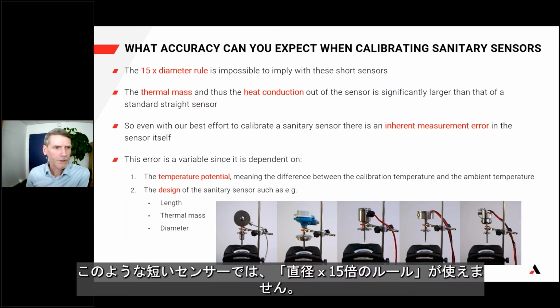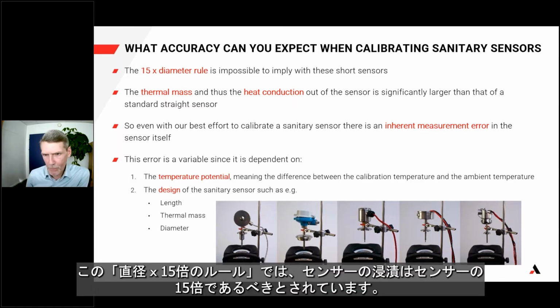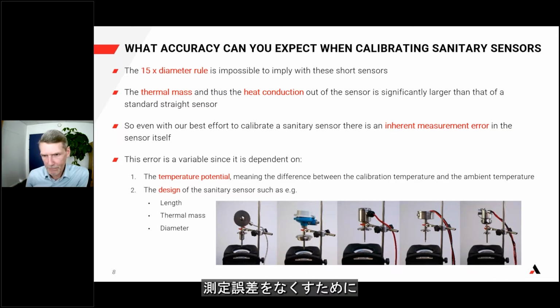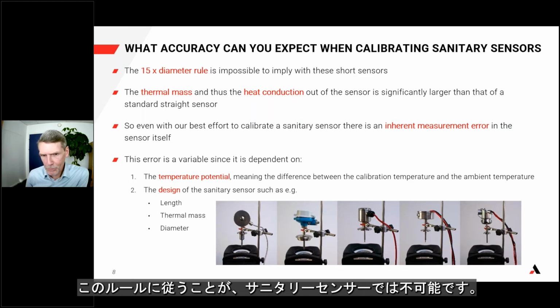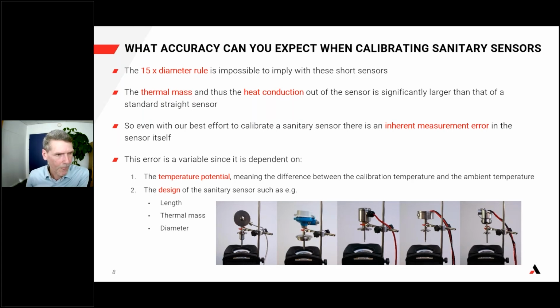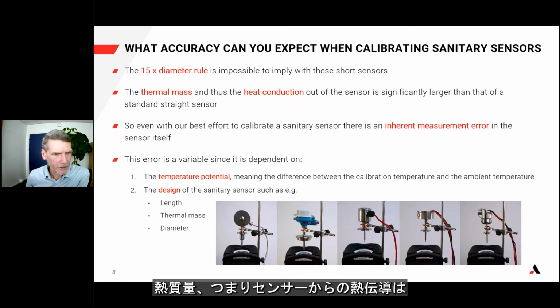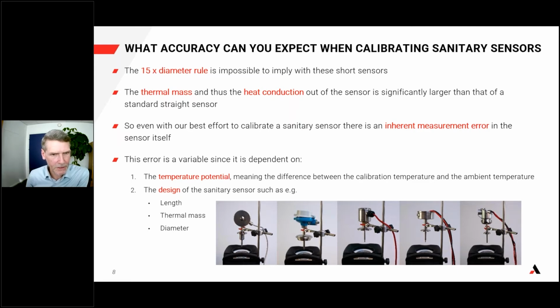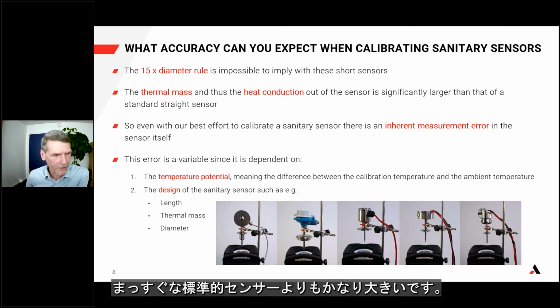The 15 times diameter rule is impossible to apply with these short sensors. The rule states that the immersion depth of a sensor should be 15 times the sensor diameter in order to eliminate measuring error. This rule is not possible to obey with sanitary sensors. The thermal mass, and thus the heat conduction out of the sensor, is significantly larger than that of a straight standard sensor.